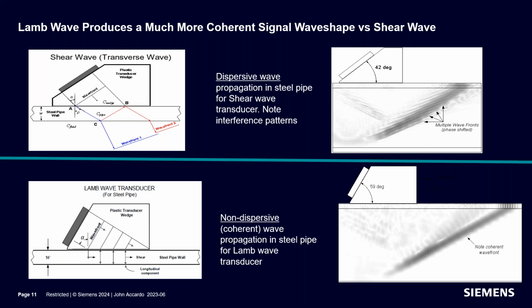And so to get a Lamb wave, you've got to match two characteristics. One, you've got to match the phase velocity of the material that you're injecting the energy into. So in this case, a steel pipe wall, you're matching its phase velocity or its speed of sound. But the second is you want to match the resonance of that pipe wall, which is relative to its thickness. So if you think of a guitar string, the sound it makes is relative to how thick it is. And that's basically what the pipe wall is. It's a guitar string. And so what we want to do is resonate that guitar string at its natural frequency. We're giving the pipe exactly what it wants. It's the pipe that dictates what it needs, not the transducer.